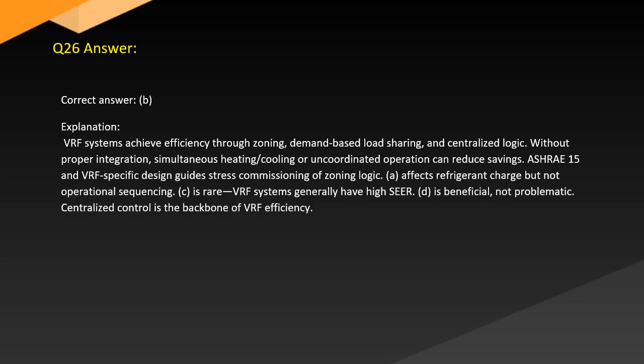Answer. Correct answer: B. Explanation. VRF systems achieve efficiency through zoning, demand-based load sharing, and centralized logic. Without proper integration, simultaneous heating, cooling, or uncoordinated operation can reduce savings. ASHRAE 15 and VRF-specific design guides stress commissioning of zoning logic. A. Affects refrigerant charge but not operational sequencing. C. Is rare. VRF systems generally have high SEER. D. Is beneficial, not problematic. Centralized control is the backbone of VRF efficiency.